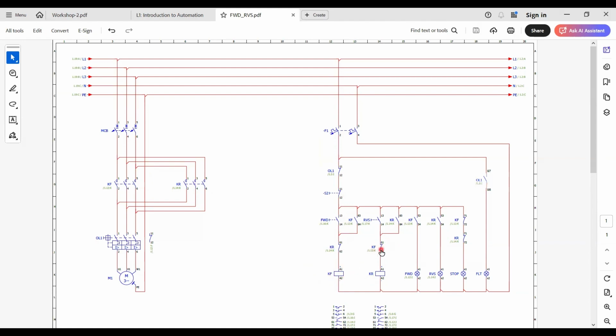That will result this KF normally closed contactor to be closed when you start the motor in the reverse direction. When the motor is running in the reverse direction, the reverse light indicator will light, based on the normally open contactor of the reverse contactor that is connected to 53 and 54 of this reverse contactor.